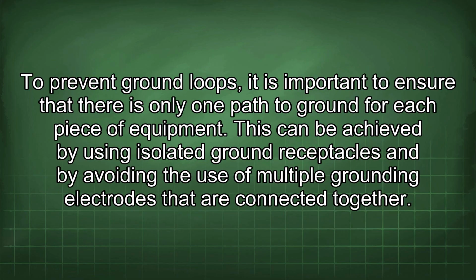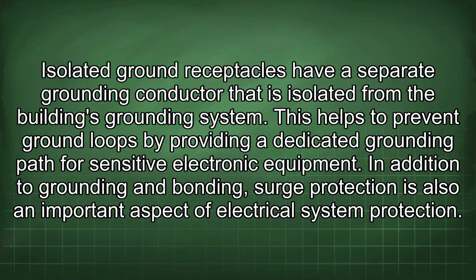To prevent ground loops, it is important to ensure that there is only one path to ground for each piece of equipment. This can be achieved by using isolated ground receptacles and by avoiding the use of multiple grounding electrodes that are connected together. Isolated ground receptacles have a separate grounding conductor that is isolated from the building's grounding system. This helps to prevent ground loops by providing a dedicated grounding path for sensitive electronic equipment.